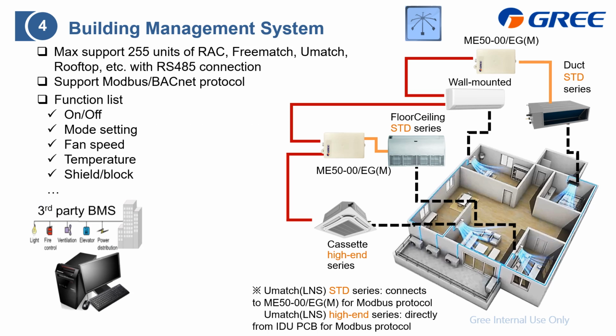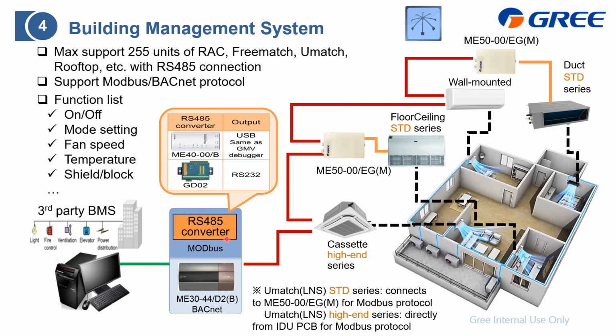This slide displays how to do the wiring to the building management system. On this picture, you can find that it is the same as the central controller, which means from the indoor unit, we need to output the Modbus protocol. For the standard model, you need to apply the ME50 as an adapter. For the high-end model or the wall-mounted, you just need to connect to the indoor unit PCB, then connect them in series. And from here, depending on your BMS system, if the protocol is Modbus, you just need the RS485 converter. For this one, we provide you the ME40. The output is USB, or the GD02 outputs RS232. As for the BACnet protocol, you need to apply this ME30. Then we can change the protocol from here, the Modbus, to here, the BACnet.